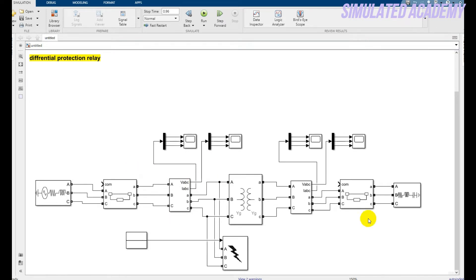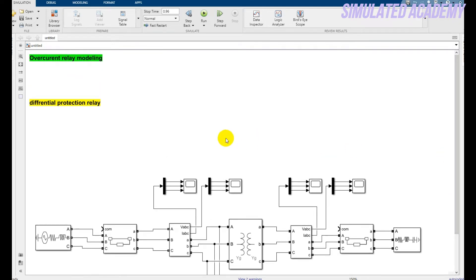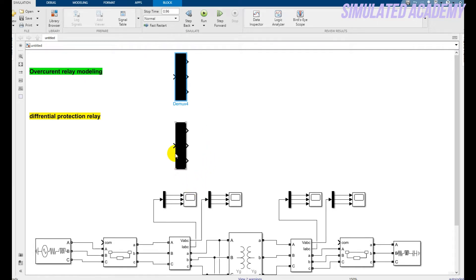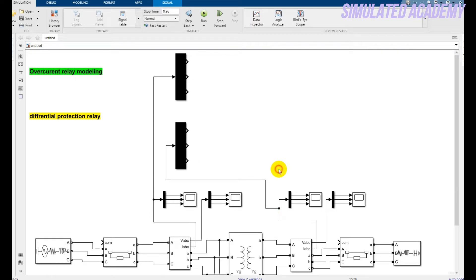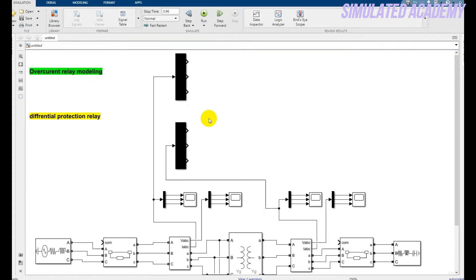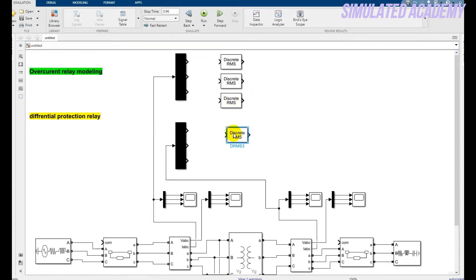Now let's design the differential protection scheme. Copy this demux block, paste it here and paste it below, just increase its size a little. Also increase the size of the other demux. After that connect input one with this current and this input with this current. Then go to the library browser, type 'root mean square', click OK, and pick the discrete RMS block. Place it here and here — copy it and place it for the below bus bar as well.